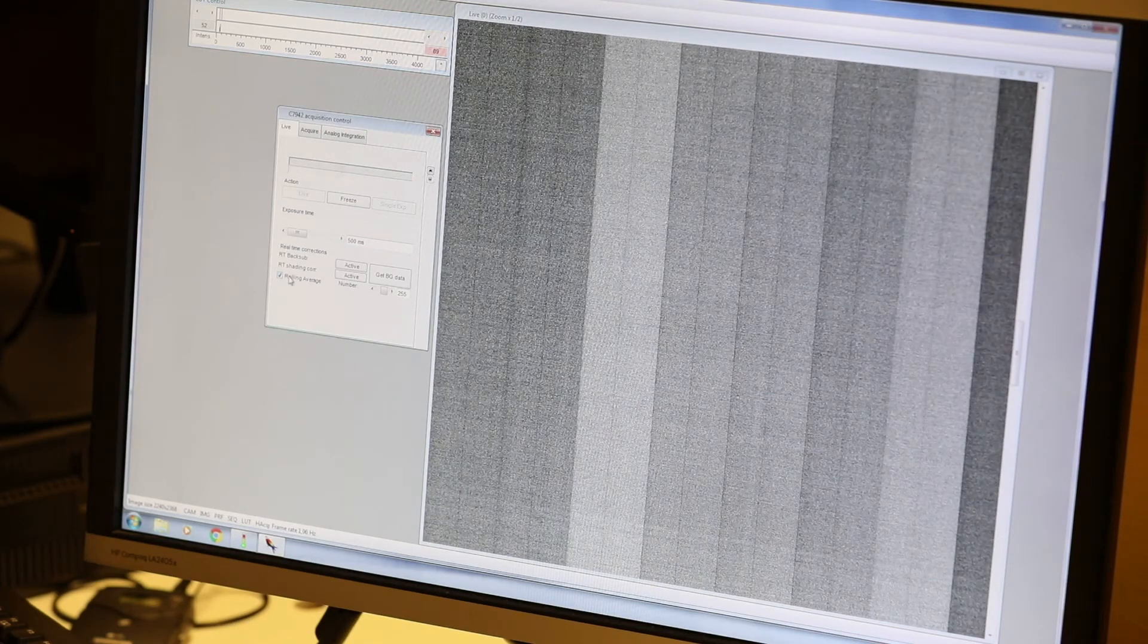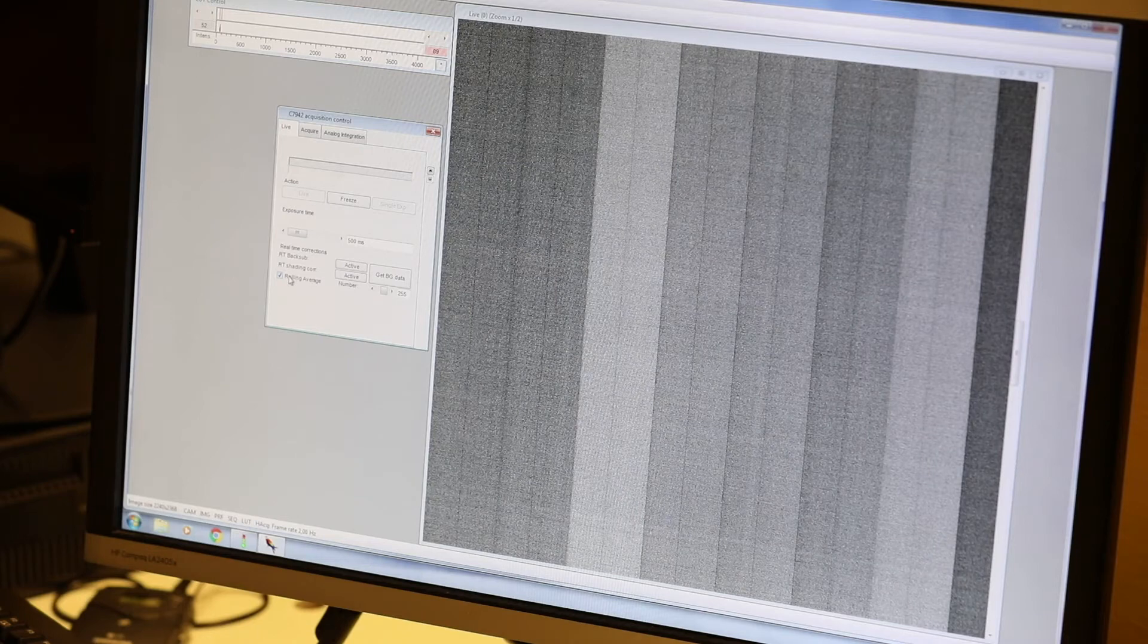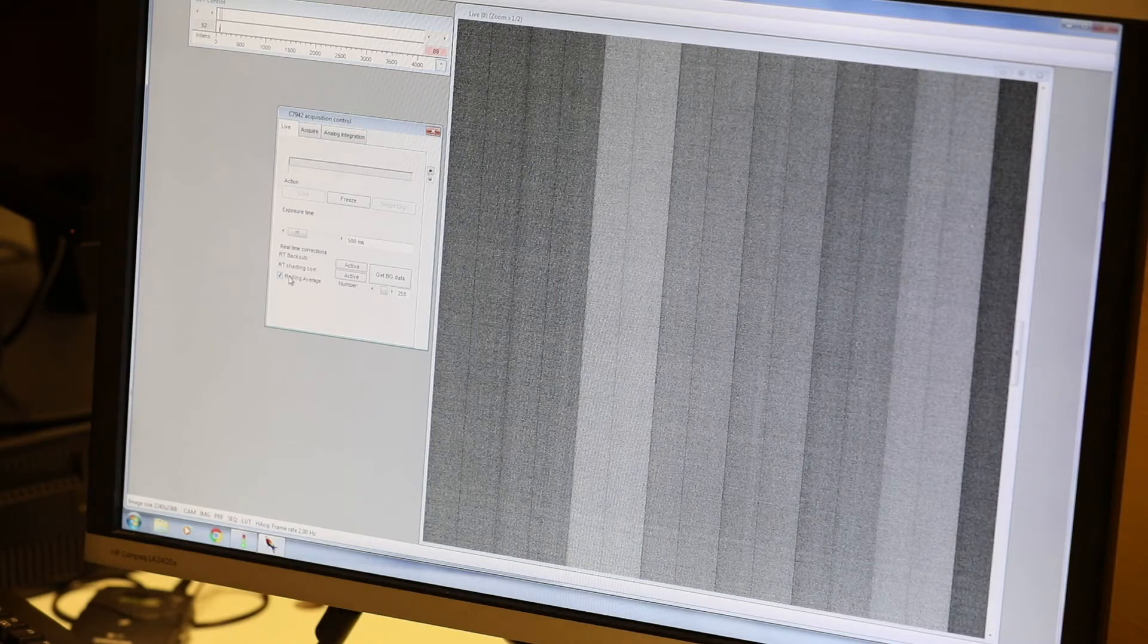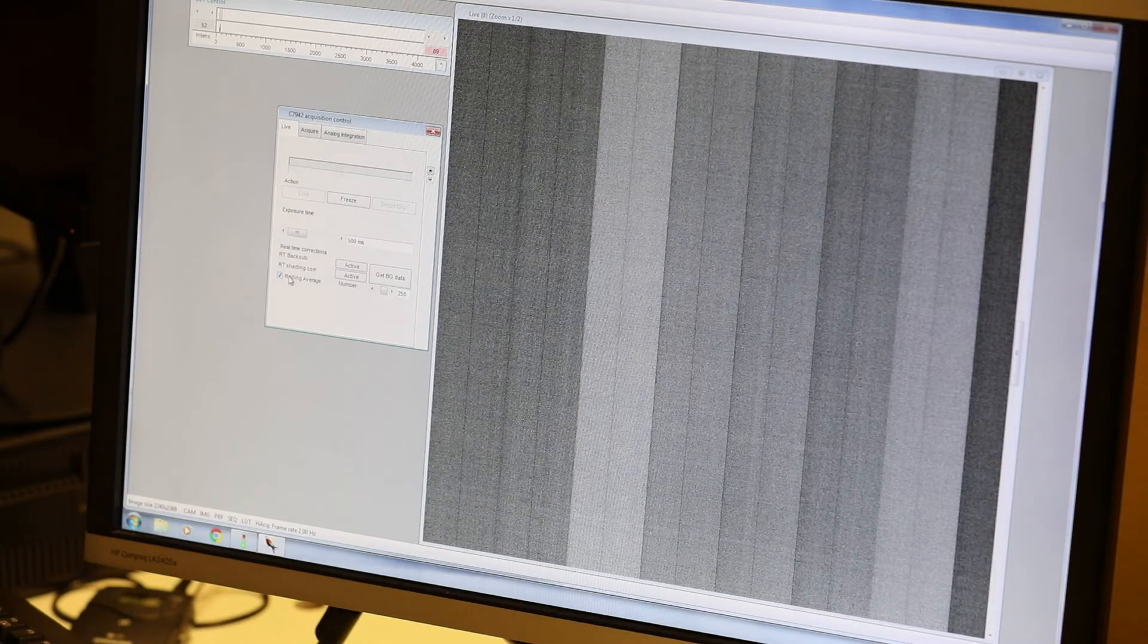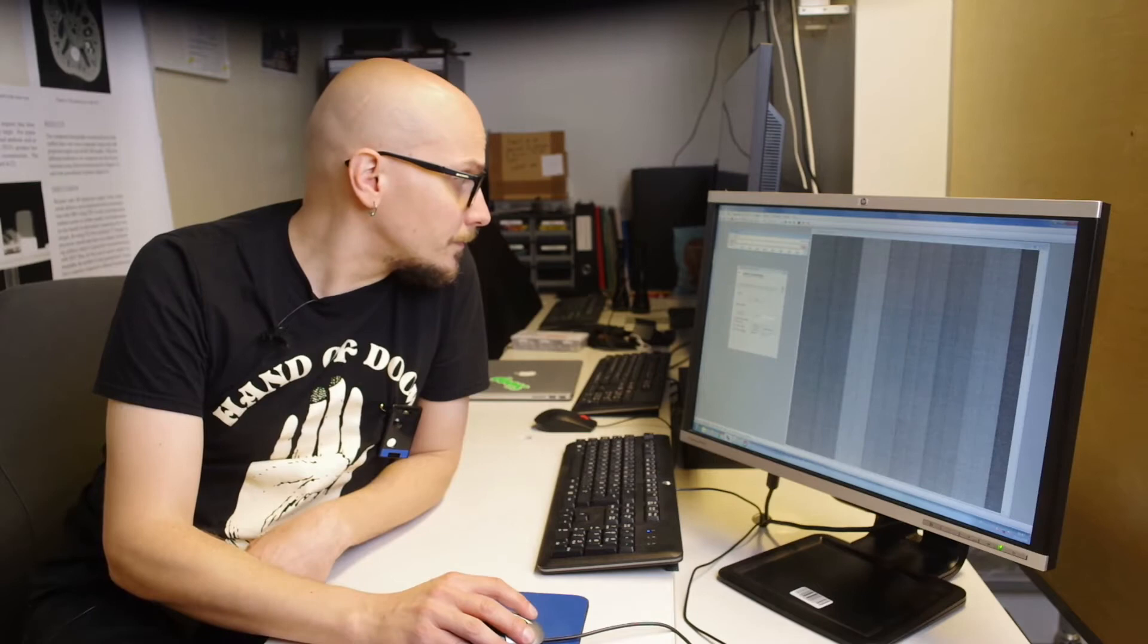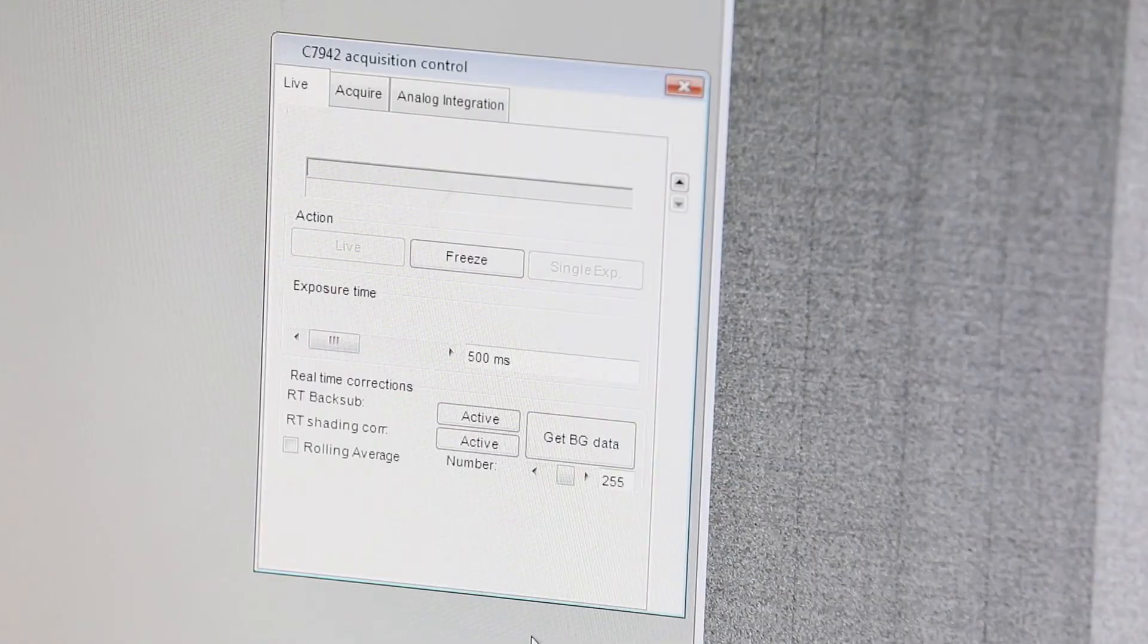Because the electronic noise isn't part of the fixed background signal, we'll get rid of it by taking the average of many dark current images. This removes the random noise and leaves the fixed vertical bands. They can be later removed from our x-ray measurements. It's important to ensure that the exposure time setting of the detector matches the measurement settings.